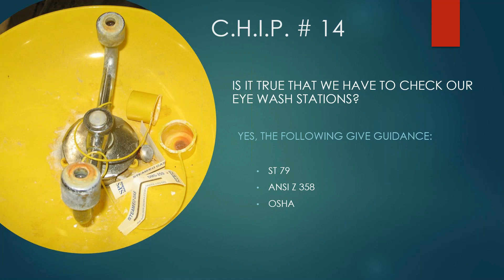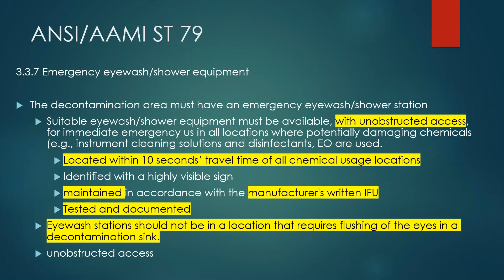What about eye wash stations? There is guidance for eye wash stations: ST 79, ANSI Z358, and OSHA. OSHA is the big one. Emergency eye wash stations should be within 10 seconds of travel time, maintained per the IFU, and testing should be documented.